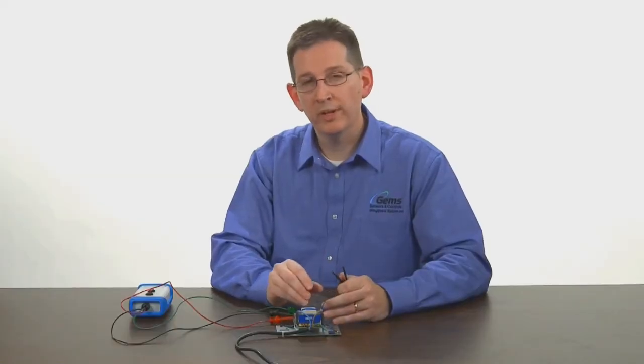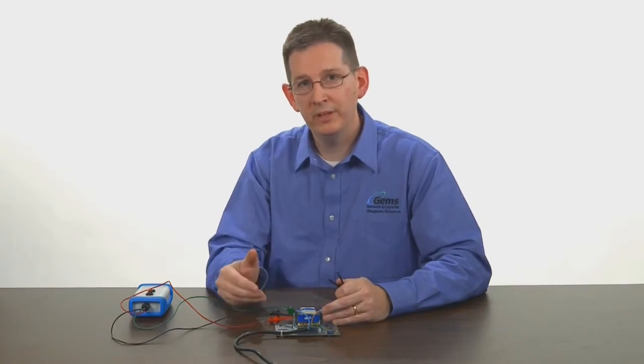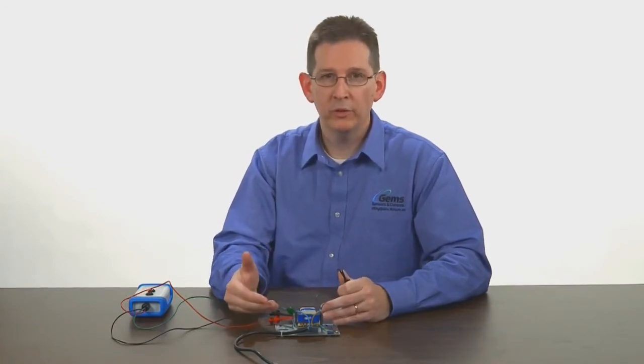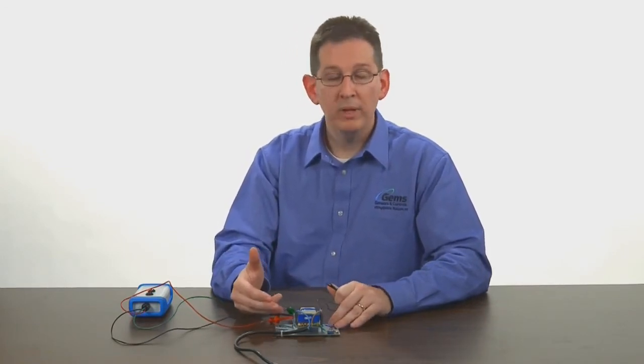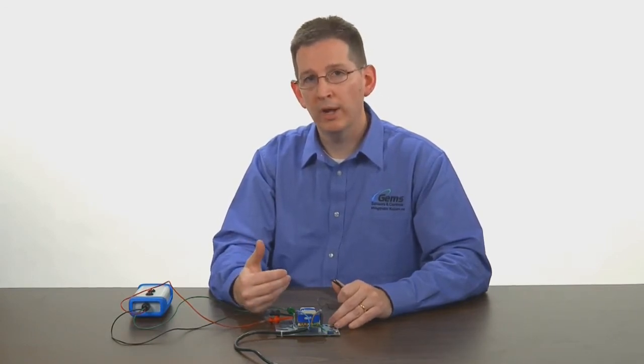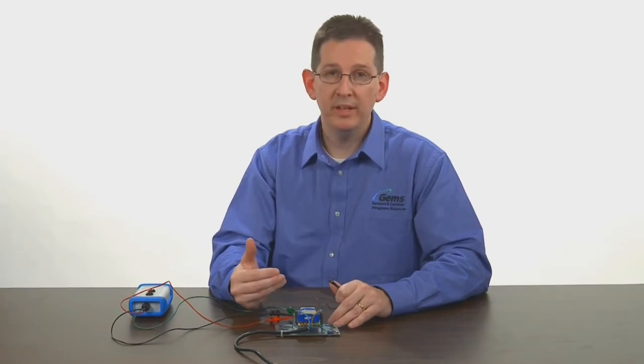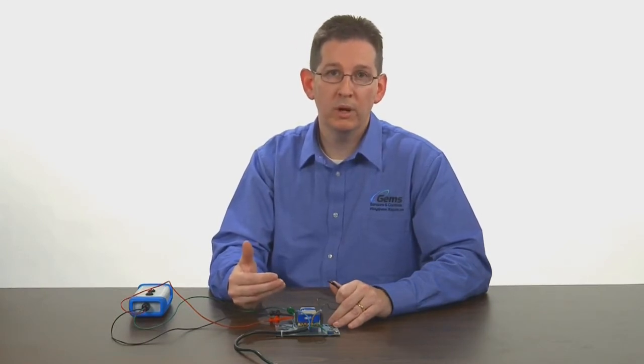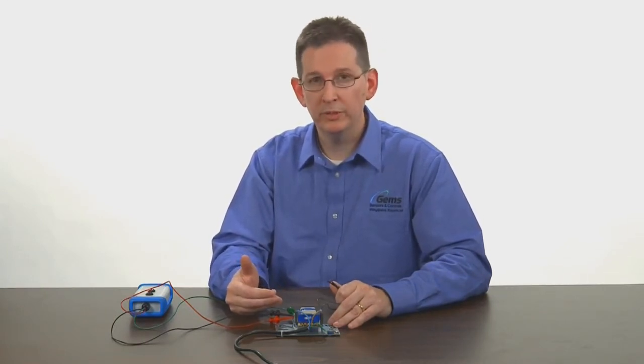This again is a direct mode unit. Should you have an inverse unit the actions are opposite meaning that the relay is energized when both probes are dry and de-energized when both probes are wet in the differential case.